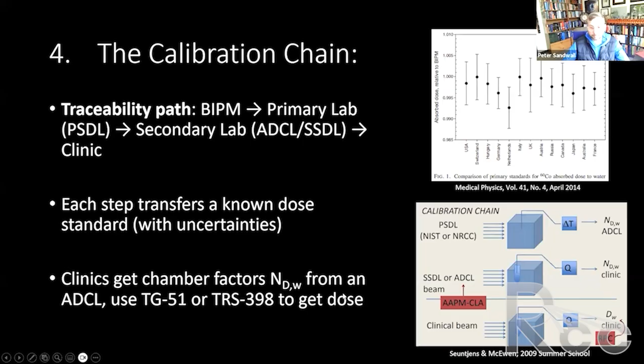Now this is still very small, but it's not zero. I think this is really important to appreciate, that there's always uncertainty in all of our measurements. That's why I'm very sensitive to the terms absolute. It's still relative. It's just relative to a standard, and we've done our best. We've worked very hard to make that range of uncertainty very small. So clinics get the chamber factors, the NDW, from an accredited dosimetry laboratory, and we either use TG51 or TRS 398 to actually calibrate our machines.